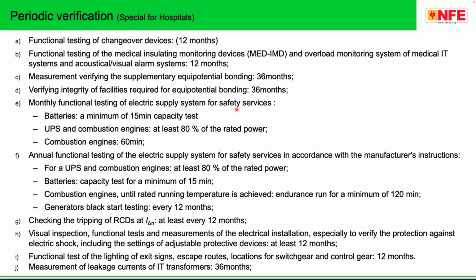Functional testing of electric supply for safety services, for firefighting, for example. The batteries are to be tested with the minimum 15 minutes capacity test. UPS and combustion engines at least 80% of the rated power. Combustion engines 60 minutes, you should do these particular tests. Annual functional test, and UPS and combustion engine at least 80% of the rated power. So I'm not going to read this.